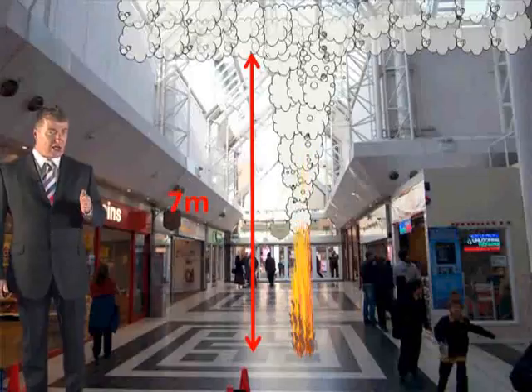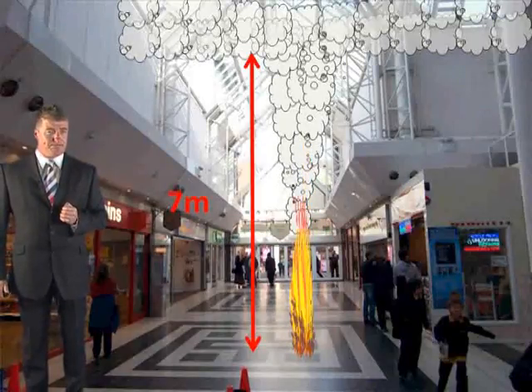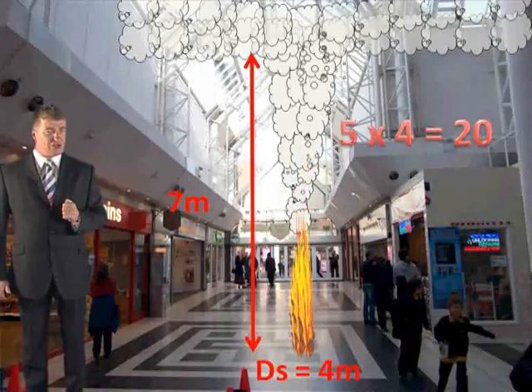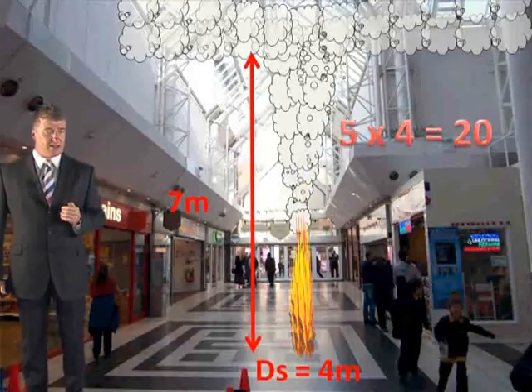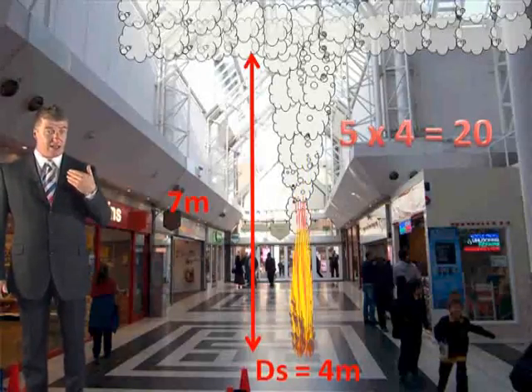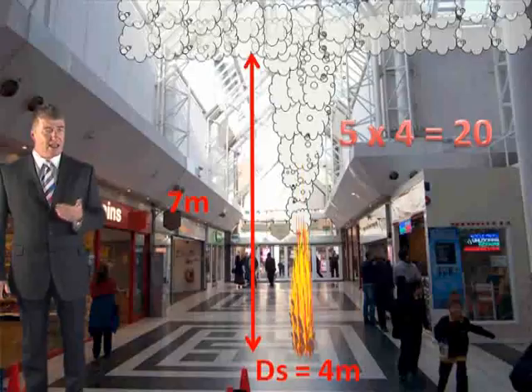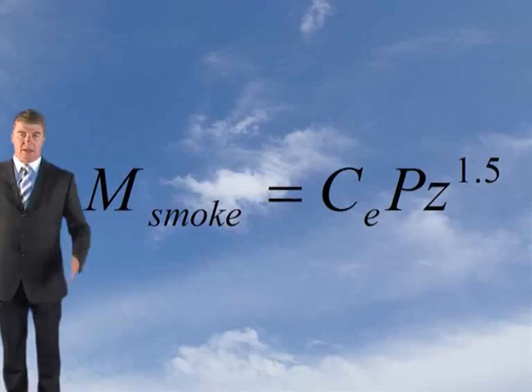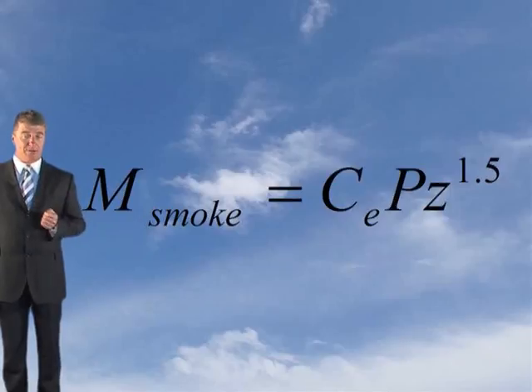Now, in this case, the clear layer height is 7 metres. 5 times the longest dimension of the source is 5 times 4, which is 20 metres. Clearly, 7 is not greater than 20, and so it's a near field. Now, here is the model available for the near field axisymmetric plume.